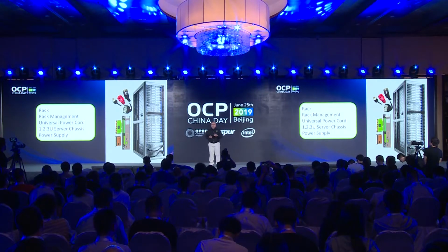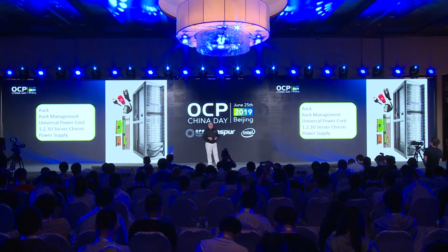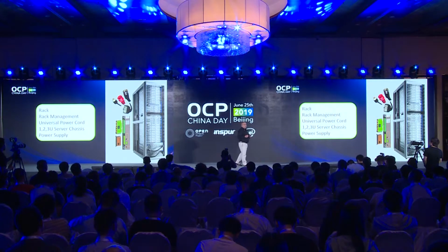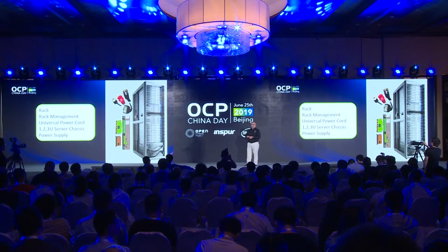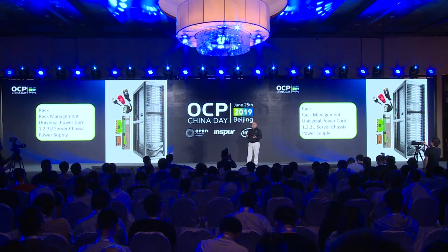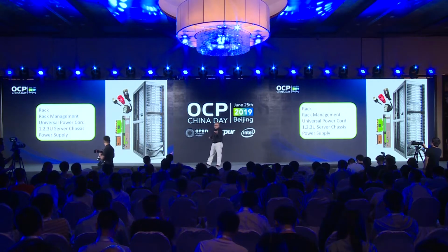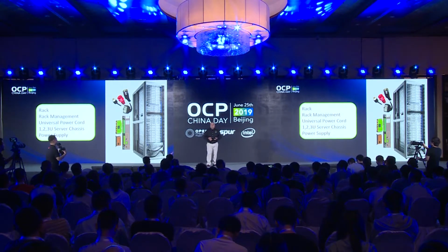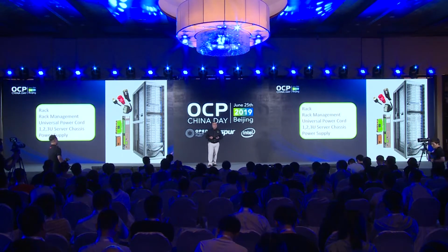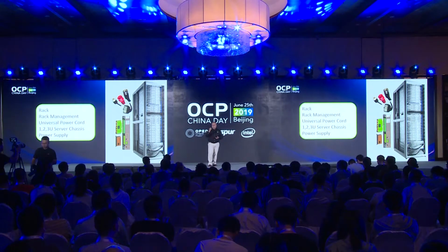In many data centers, the actual power connector is a different shape, has different pins, different polarities, and so they designed a system where the power cord was interchangeable. So on the day of deployment, they'd pick the right power cord, plug it into the rack, and it would power up. At the same time, on the back of the rack, they also designed a power distribution system. It takes that power cord, converts the signals, the proper signals, to distribute AC power to all of the server nodes.